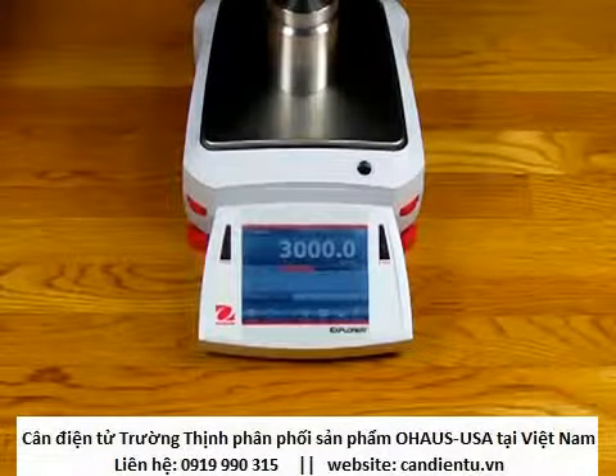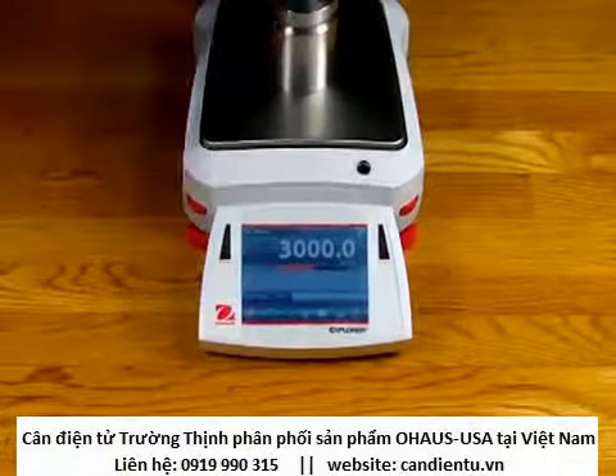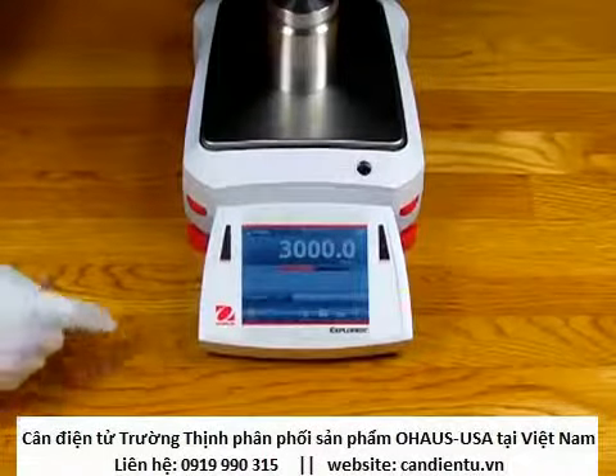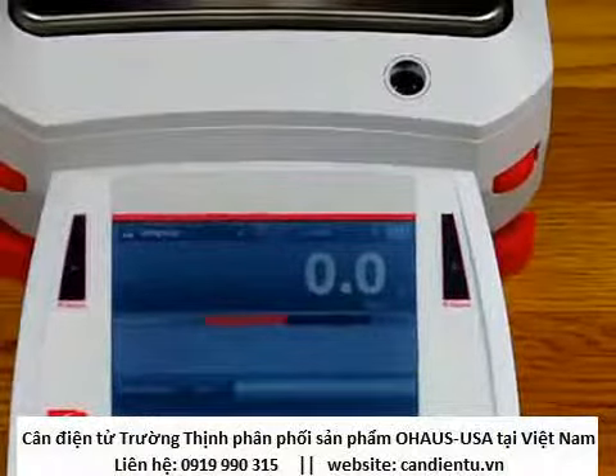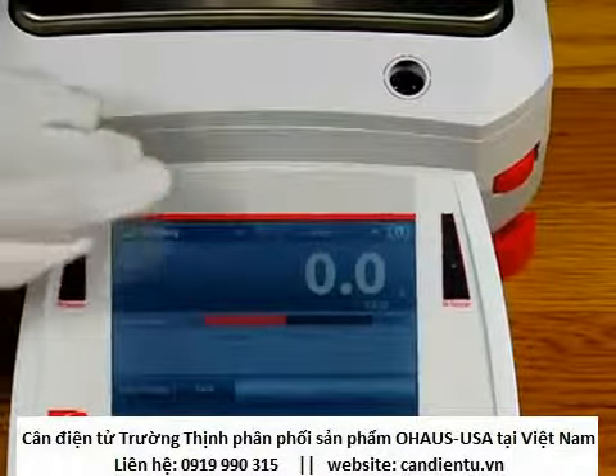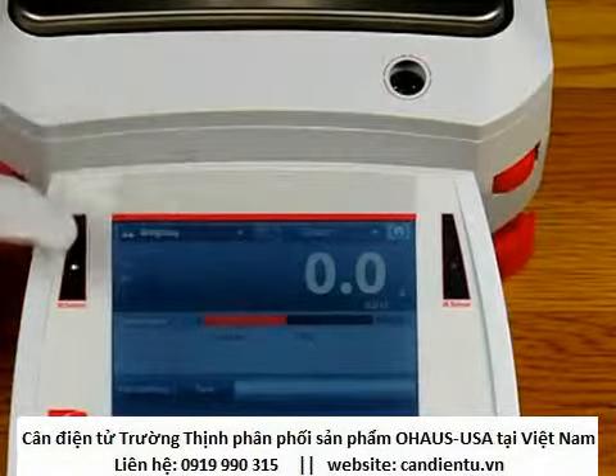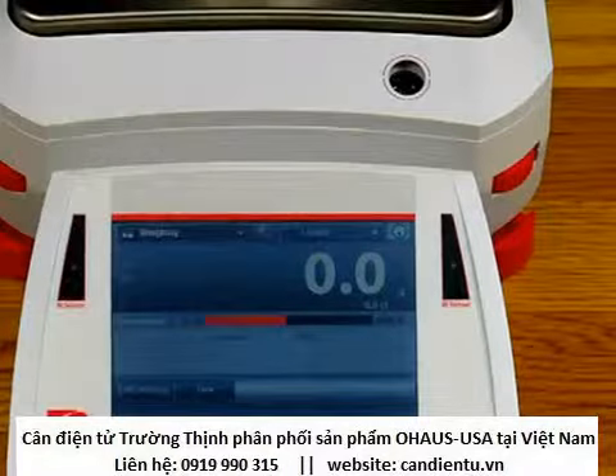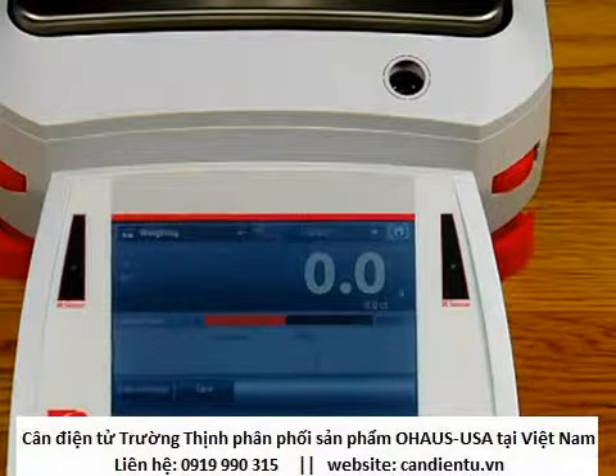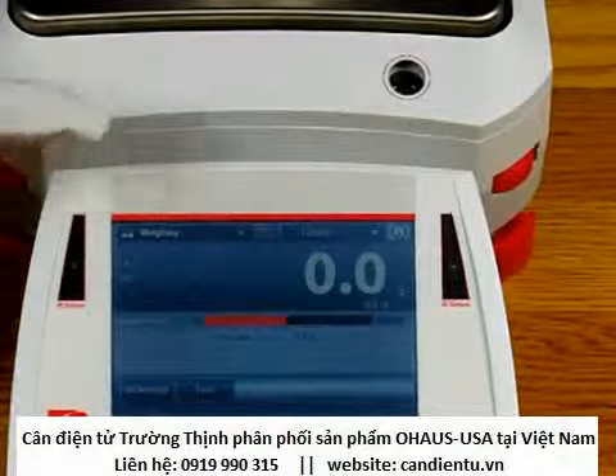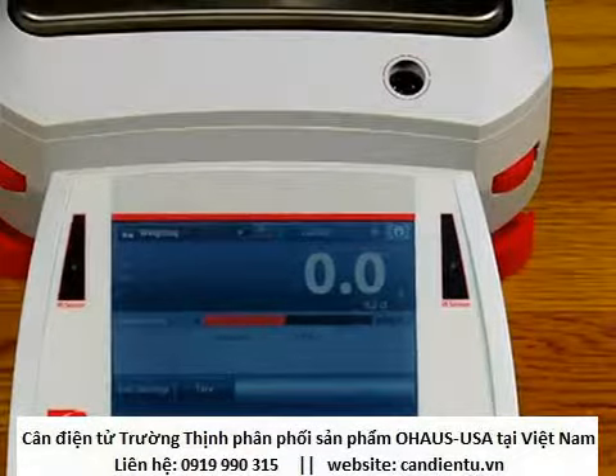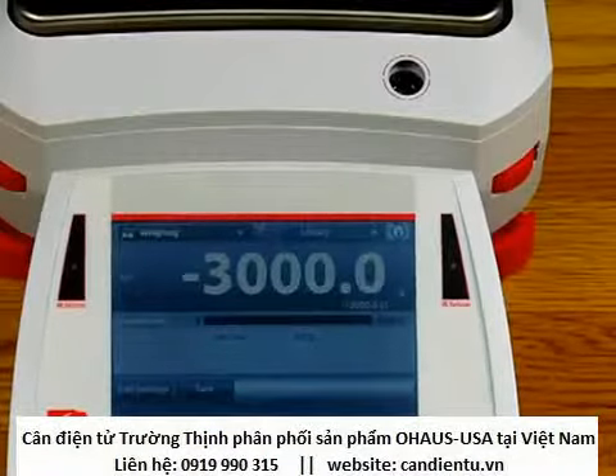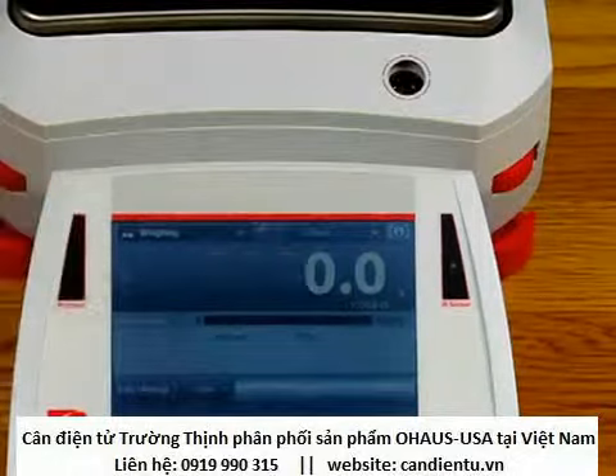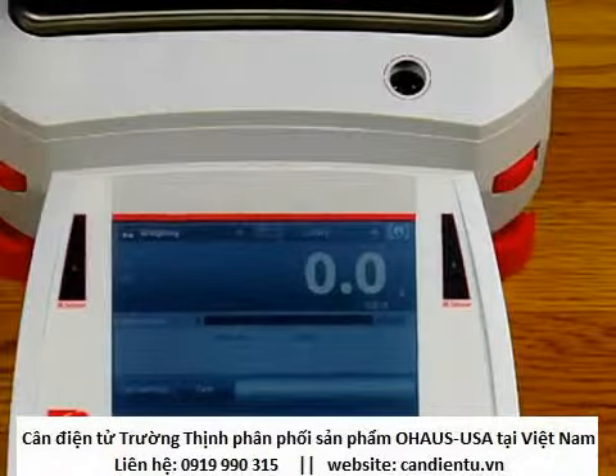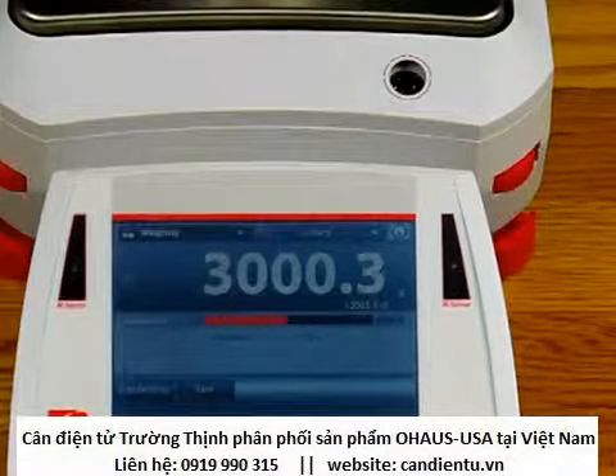Here on this balance we're showing 3,000 grams, and we have a second weigh unit below showing 15,000 carats. Notice I just put my hand over it - there are two sensors on the balance that zero it out. When I move my hand over this sensor, it zeroes out. So if I take the calibration weight off, zero it out again, and put the weight back on.